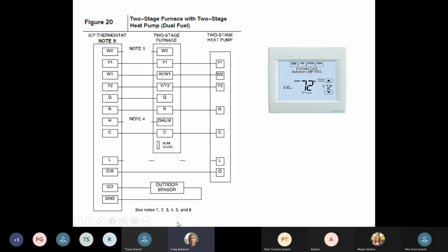I always like an outdoor wired thermostat. I don't like using Wi-Fi, anything like that. Outdoor sensor, wired, you run it outside by your heat pump that's outside. Wi-Fi is taking the temperature of whatever the world's telling us at that point. But your heat pump could be sitting on the south side of the house in the sun at that time of day when it's -25 outside, but your heat pump is actually sitting in the sun and it's only -10. Hey, we could be running that baby and saving these people money.